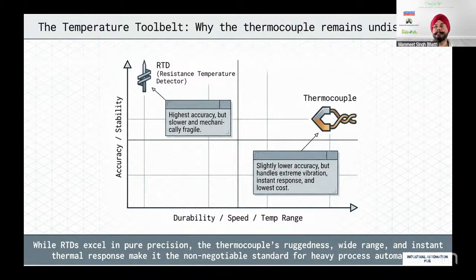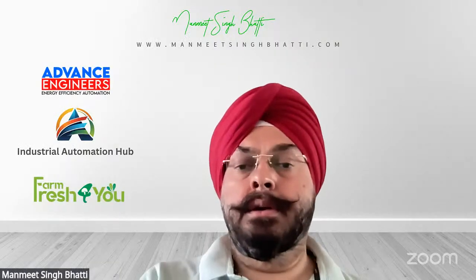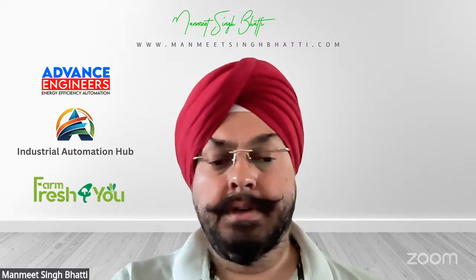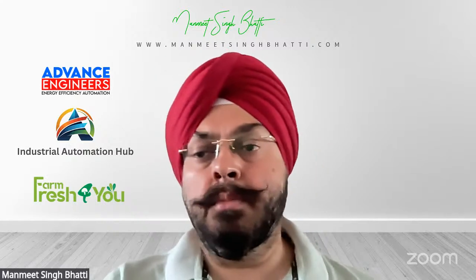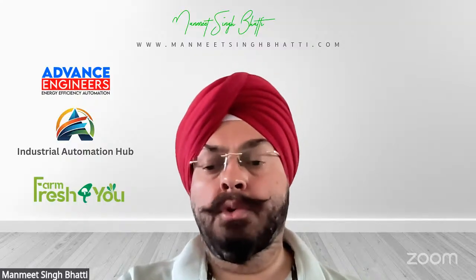Normally, what I see is whenever an RTD can fit into the picture, always go for an RTD, because in instrumentation it means more accuracy. But if you have an application where you need a rugged sensor, a very high profile sensor, which cannot fail, where your process is very, very important, always go for a thermocouple. So this is what we have on the thermocouple part. If you have any questions on the thermocouple part, I will be more than happy to answer.